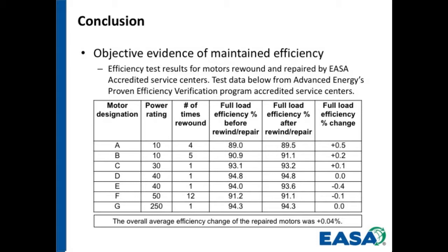And if you're doing efficiency testing and trying to compare, especially if it was what they would call a round robin, going from one facility to another to be tested, the usual rule that I've heard is about any variation that's plus or minus 0.2%. It's really not telling you there's a difference. So there's a couple, the minus 0.4 and the plus 0.5, that might say there's something that's been done to the motor that either affected it negatively or affected it positively. But overall, it's really no change.